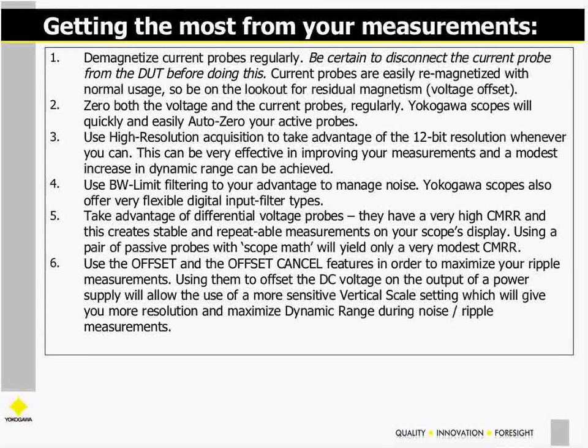Use a high-resolution acquisition mode if you can. Each of our current production scopes has a high-resolution mode, a method that takes an 8-bit measurement up to either 9, 10, 11, or 12 bits of resolution. It's an averaging-type method. Your waveform doesn't have to be repetitive. This can improve your dynamic range a little bit, and certainly the repeatability of your measurements.